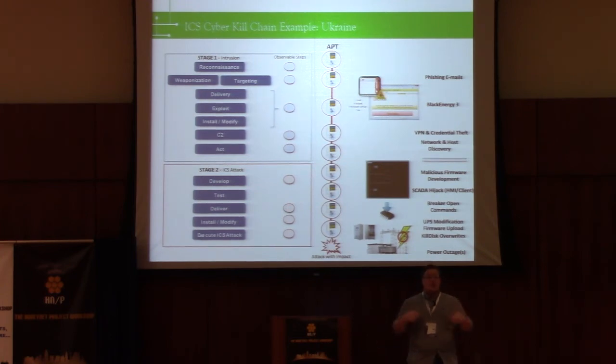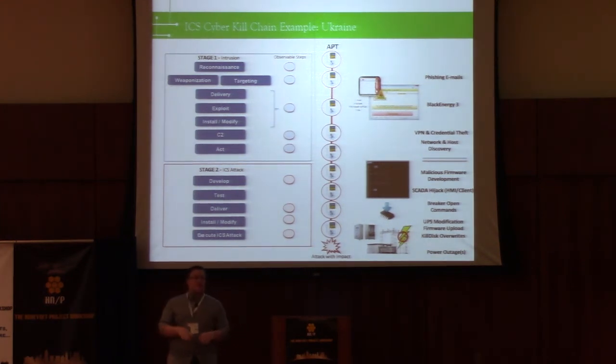The adversaries then used those VPN credentials to go into the control system environment itself, which was separated off from the business network. When they went into the environment, they spent 6 months inside those different environments, 3 different Oblenergos, to learn the environments, to do the asset discovery, to figure out the data flows, to try to determine how they were implementing their SCADA DMS. The SCADA distribution management system, the DMS, there were 3 different ones. 2 you'd probably only find in Ukraine, 1 you would find anywhere in the world.